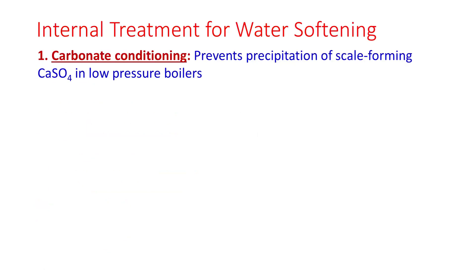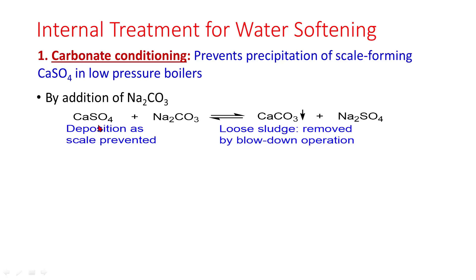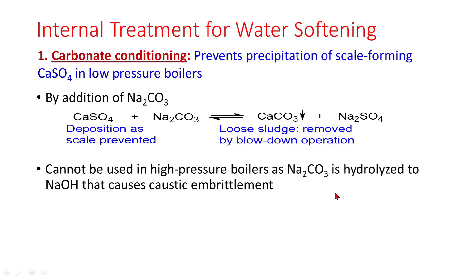Carbonate conditioning prevents precipitation of scale-forming calcium sulphate in low pressure boilers. By the addition of sodium carbonate, calcium sulphate deposition as scale is prevented, which gives rise to calcium carbonate, which is a loose sludge and can be removed by blowdown operation.